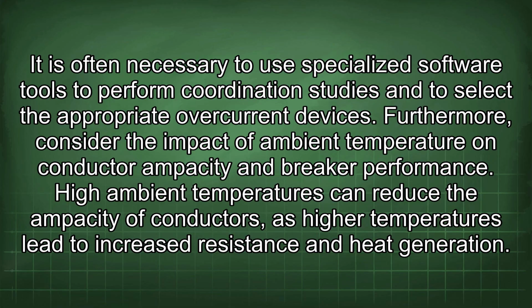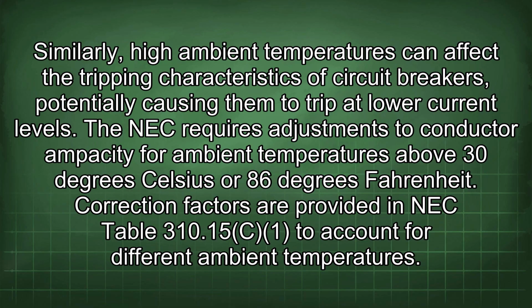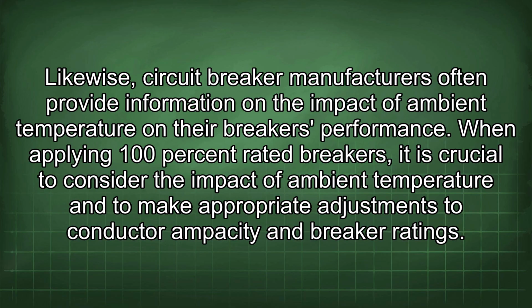Furthermore, consider the impact of ambient temperature on conductor ampacity and breaker performance. High ambient temperatures can reduce the ampacity of conductors, as higher temperatures lead to increased resistance and heat generation. Similarly, high ambient temperatures can affect the tripping characteristics of circuit breakers, potentially causing them to trip at lower current levels. The NEC requires adjustments to conductor ampacity for ambient temperatures above 30 degrees Celsius, or 86 degrees Fahrenheit. Correction factors are provided in NEC Table 310.15 to account for different ambient temperatures. Likewise, circuit breaker manufacturers often provide information on the impact of ambient temperature on their breakers' performance. When applying 100% rated breakers, it is crucial to consider the impact of ambient temperature and to make appropriate adjustments to conductor ampacity and breaker ratings.